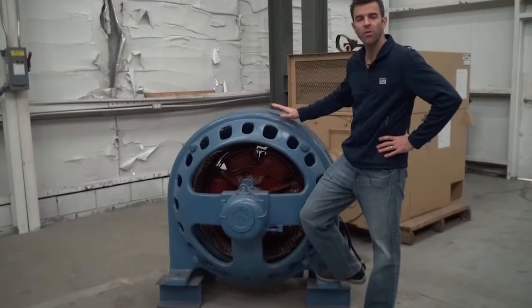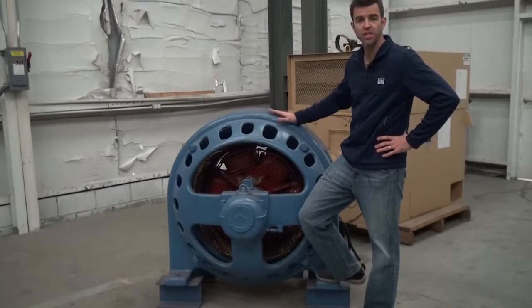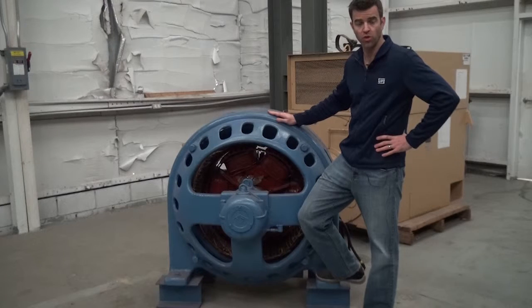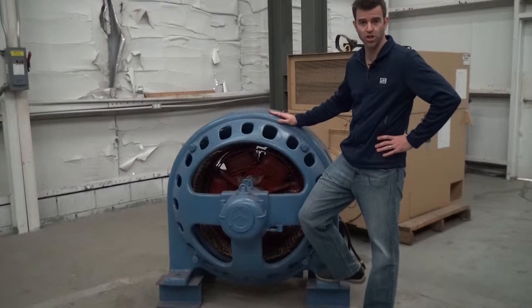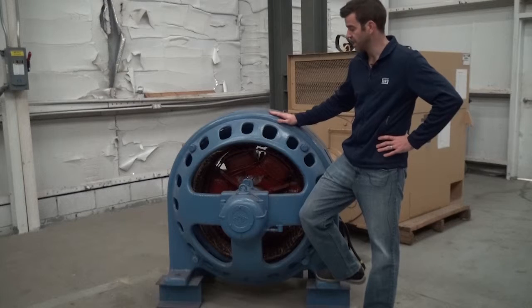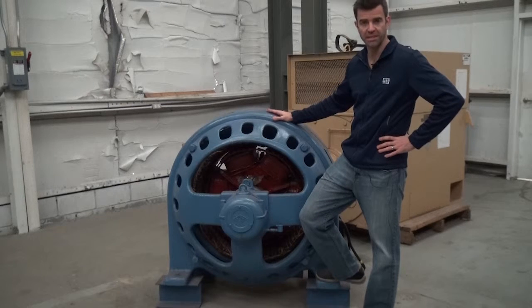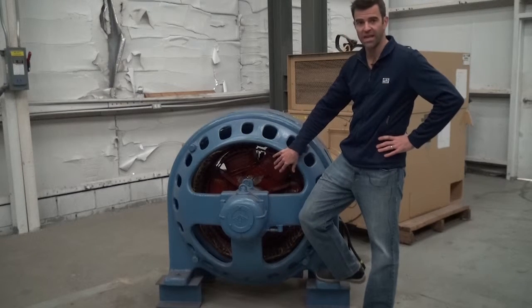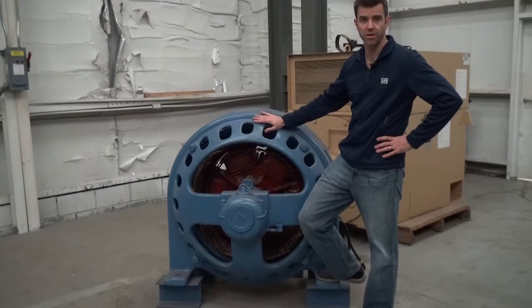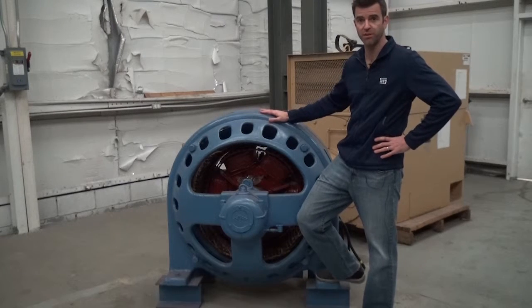In the following training modules, we'll discuss the details of a synchronous motor. Here we have a synchronous motor. This is a much older model than you'll normally be working on, but it's ideal to show the different components of the assembly. This synchronous motor is an open type, which is why you can see the windings. This is not common on modern assemblies, which have to be protected for safety reasons.